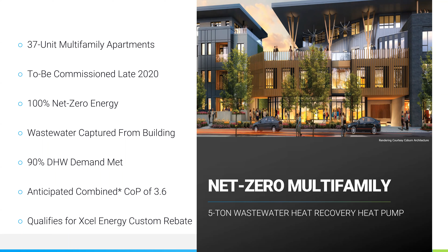The next slide really hits it home for developers pursuing net zero design. Even though this project is in a location with relatively small heating and cooling loads, the loads are even smaller because of how net zero buildings are constructed, with much less heat loss, requiring less space heating and cooling. So what really drives the energy load is the domestic hot water system. That becomes very important on a multifamily building 3-4 stories tall, since you don't have infinite roof space to achieve net zero. So the goal is the lowest energy consumption possible, to get as close to net zero as you can given the roof space available.